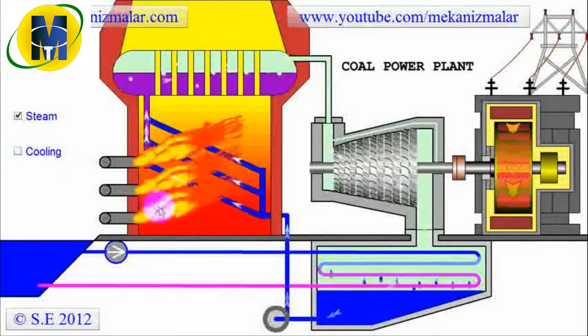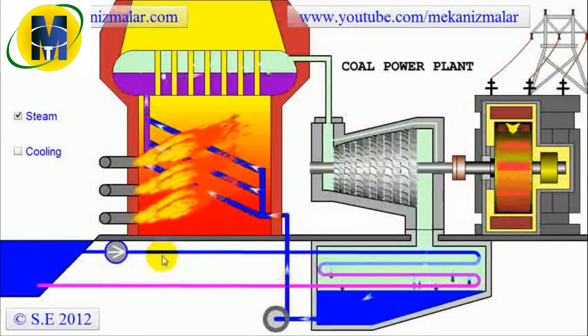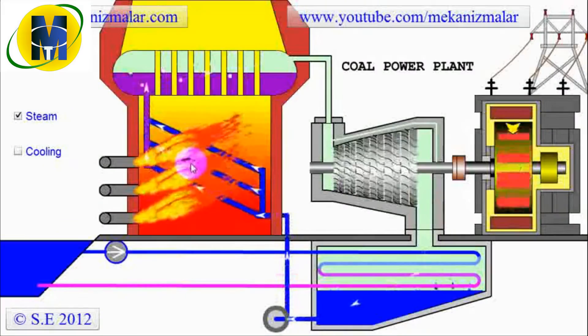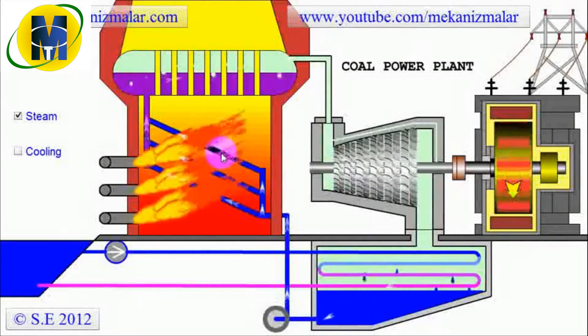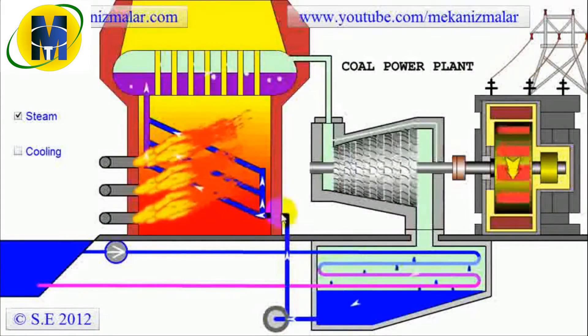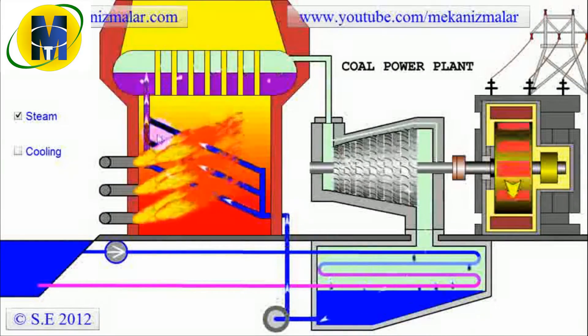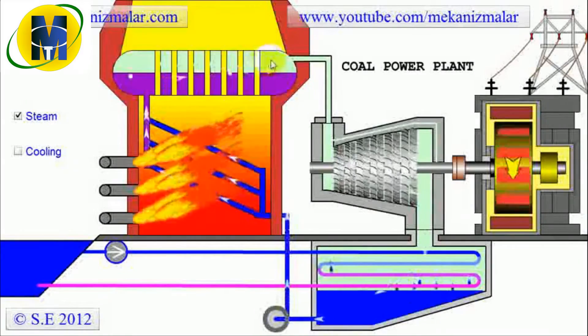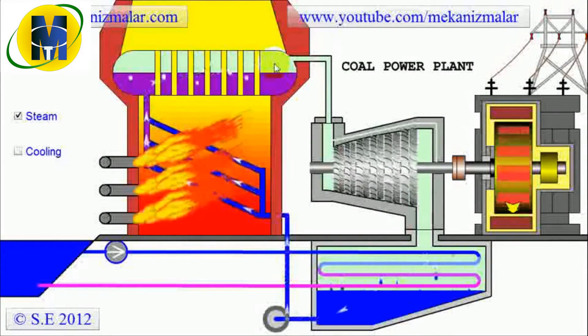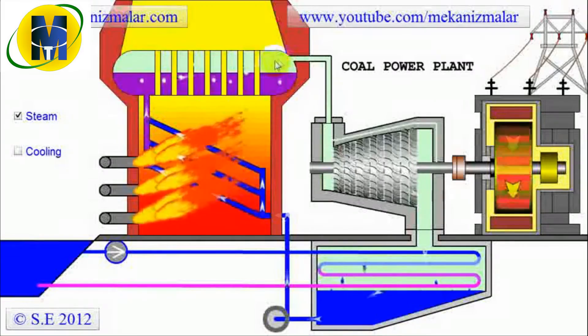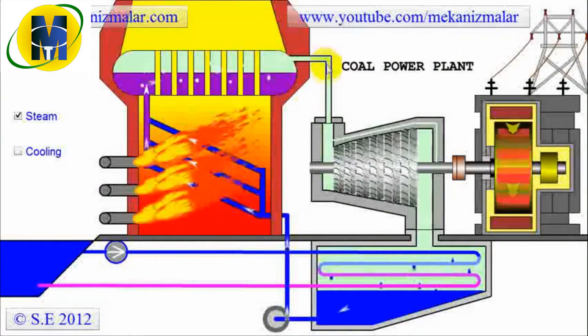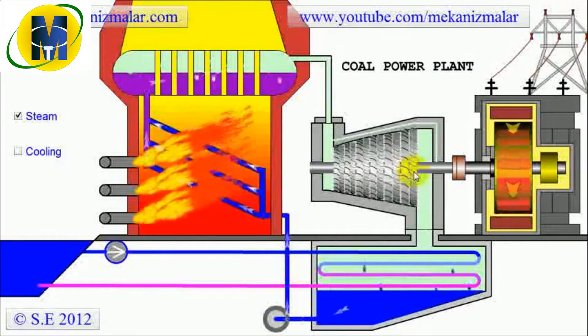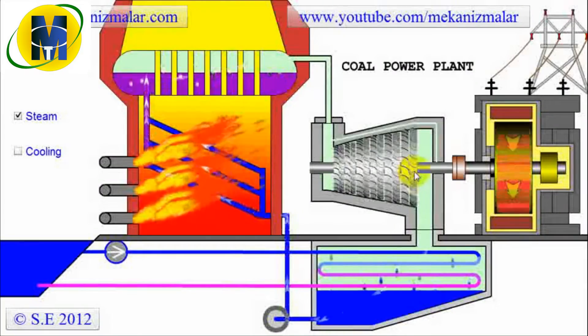Let's begin by describing the closed loop power cycle, or the steam cycle, starting from the furnace. First, intense heat inside the furnace heats the water within the coils, which is coming from the condenser. This heated water is forced to the boiler where it evaporates. The pressure inside the boiler can be more than 200 bars. The high pressure steam obtained in the boiler is sent to the steam turbine, which passes the steam between fixed and rotating sections, converting the energy stored in the steam to mechanical energy.